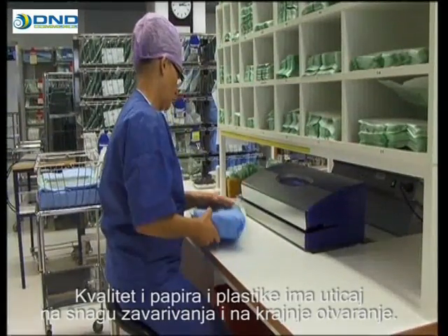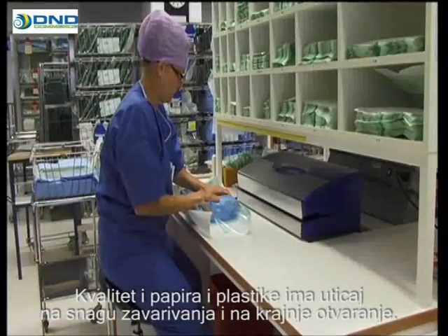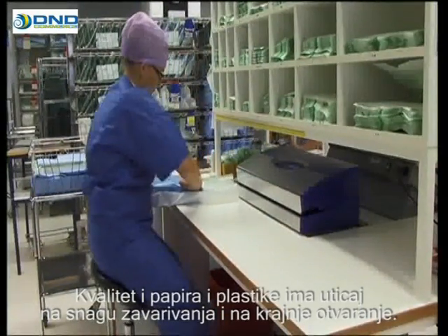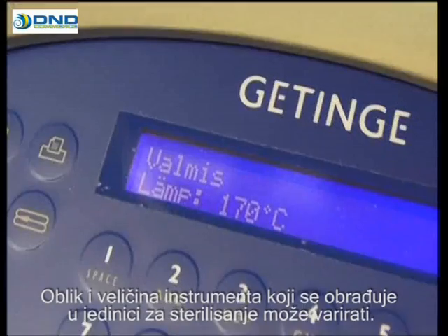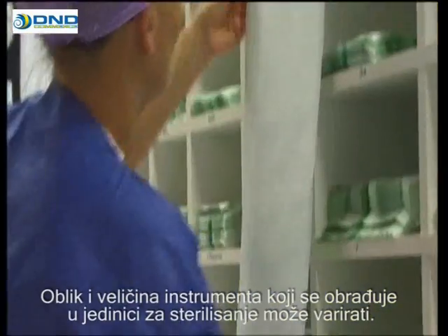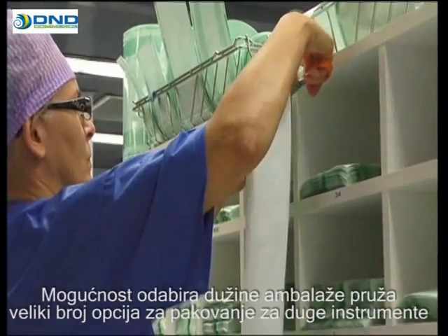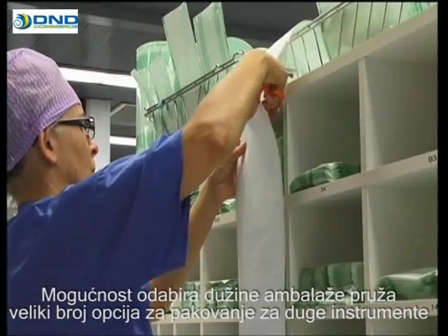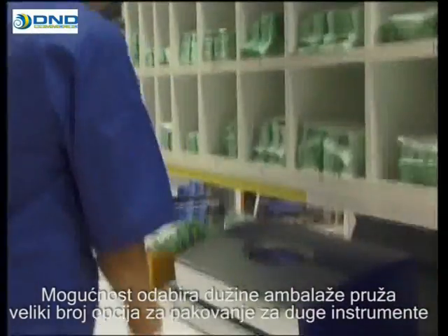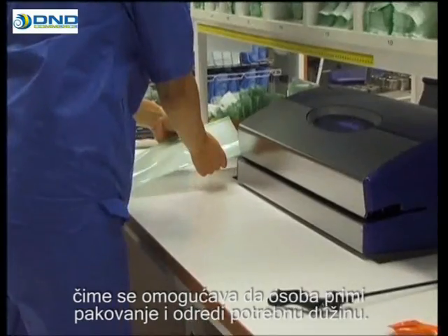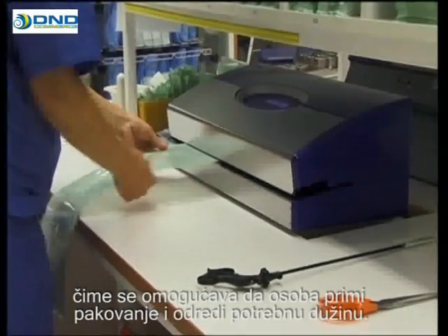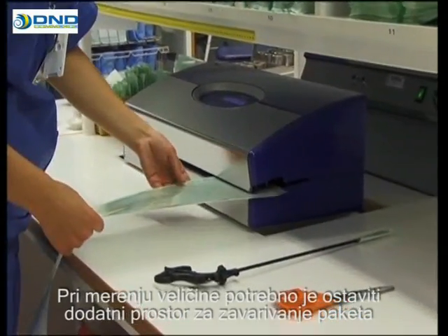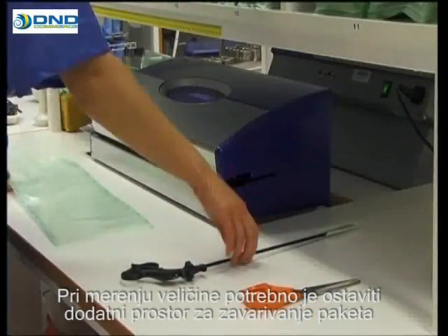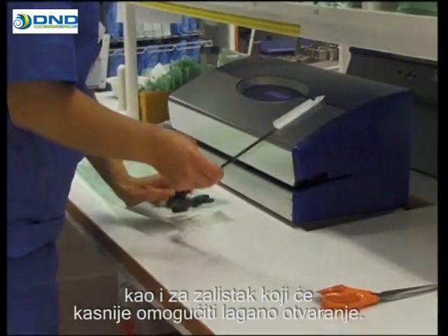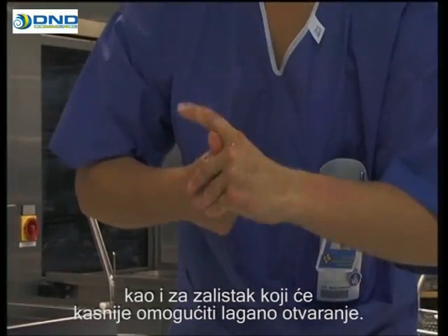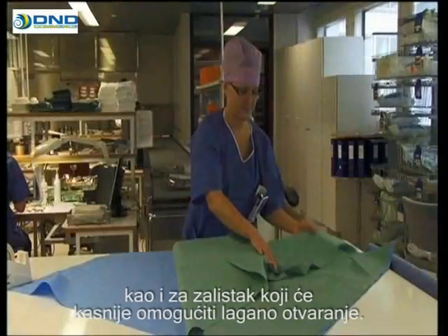The quality of both the paper and the laminate has an impact on seal strength and fiber-free opening. The shapes and sizes of instruments treated in sterilization units can vary. An open-ended roll stock pouch provides a flexible option for packaging long instruments. This enables the person preparing the packaging to determine the length needed. When measuring the size, it's important to allow extra space for sealing the package and also for a flap with which the package can then be easily opened.